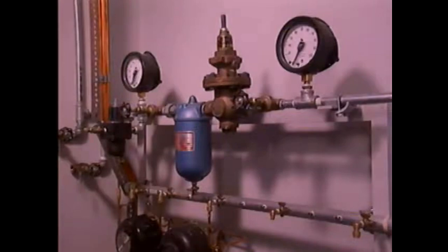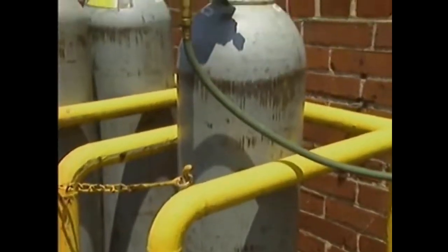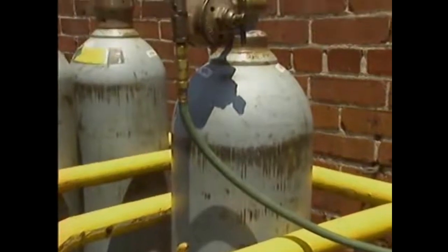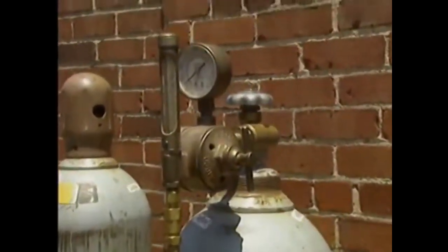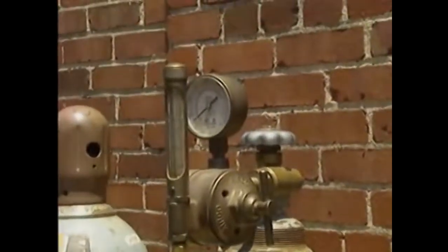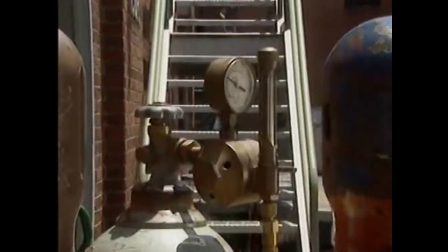This reduced the pressure sensed by the control system, which caused the control system to indicate no level in the tank. The control room operator has the nitrogen bank that supplies nitrogen to the rotometer checked. When this is done, he is told that the tank currently supplying nitrogen is nearly empty. To correct the problem, another nitrogen tank is placed in service.